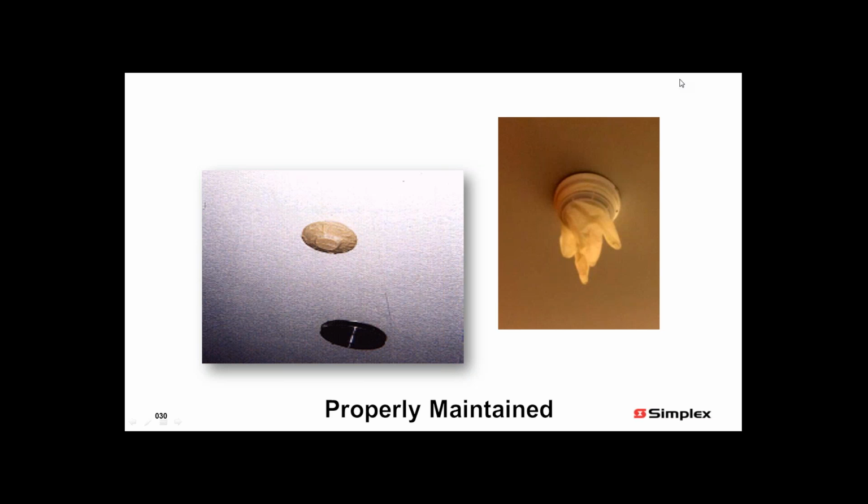So here's just a couple of pictures that we have. This one was a picture I took in a facility, and I had asked about the tape that they had over the smoke detectors, and it was in the back of house, and somebody had said that that tape has been on there for a long time because it's been years since the ceiling was painted.